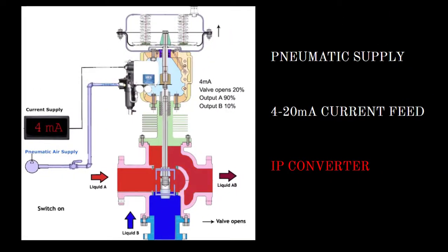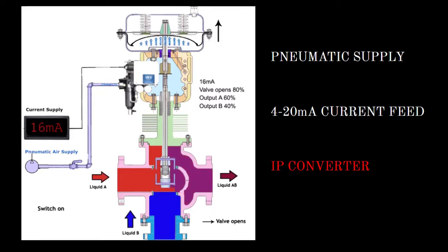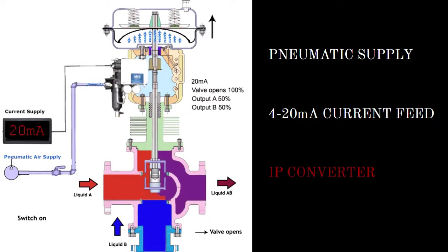When the current feed gets increased, the valve gets actuated more. The valve will open as a percentage with respect to the increasing power feed. When the current is fed to the IP converter, it will control the flow of air to the valve.